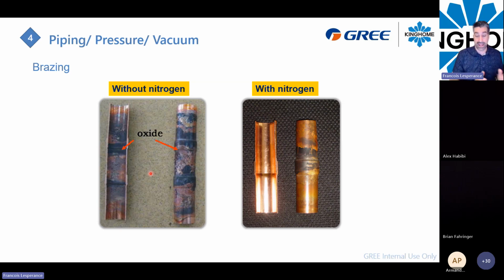inside the system, in the indoor and the outdoor unit, some strainers to protect the EEV or the TXV. This scale will mix with the refrigerant, and the refrigerant will act as a solvent and dissolve this scale into a small powder. That will block small orifices, such as your TXV and EEV, and it can also be lodged in the base of the compressor, so that will create issues with the system at any point in its life, with scale moving inside the piping.